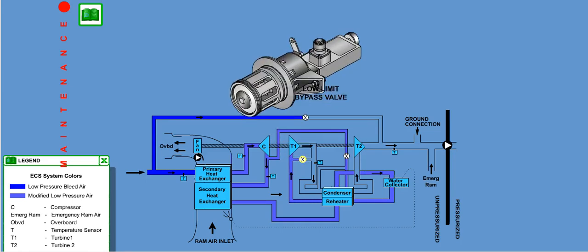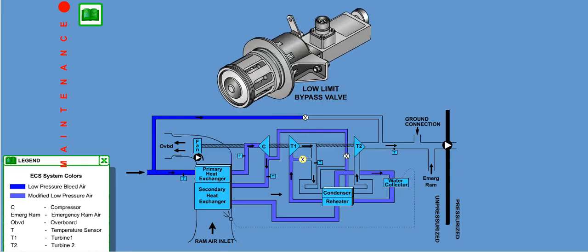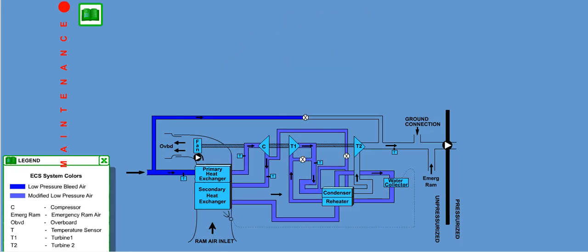The low-limit bypass valve is installed parallel to the first stage turbine. The valve provides additional warm air to maintain condenser inlet temperature. Air flows through the condenser and enters the second stage turbine for a further temperature reduction. Turbine outlet cold air is mixed with pack bypass air to achieve the requested duct temperature.